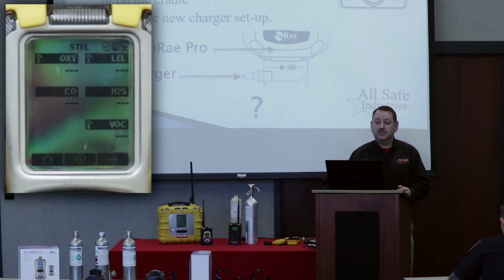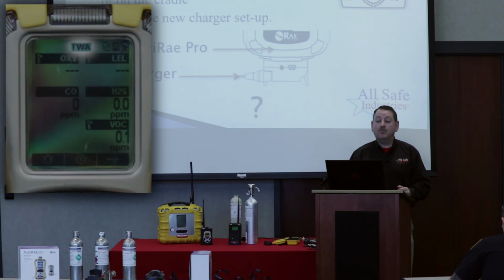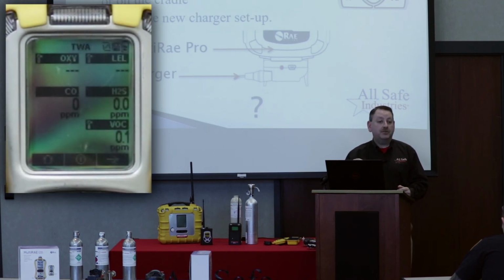Hit your arrow button again. What's the next screen say? TWA stands for time-weighted average. This is the related page to the short-term exposure limit, except time-weighted average is your 8-hour reading. So what the instrument does is it calculates based on your current exposure. If you stay at this level, your reading will eventually reach a time-weighted average. So think of that as your 8-hour reading, okay?